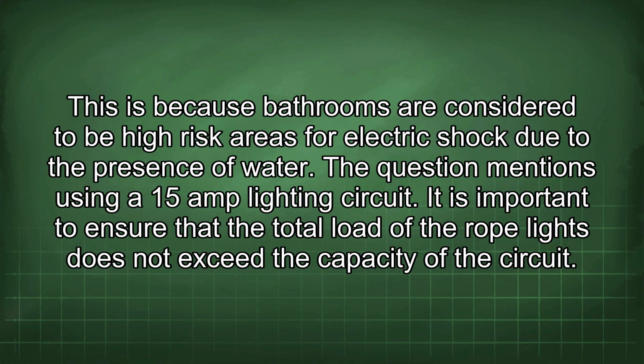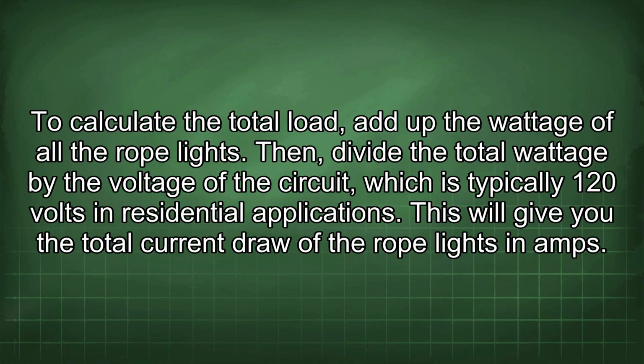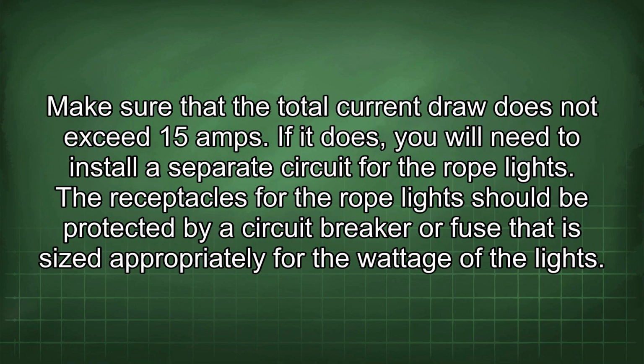The question mentions using a 15-amp lighting circuit. It is important to ensure that the total load of the rope lights does not exceed the capacity of the circuit. To calculate the total load, add up the wattage of all the rope lights. Then divide the total wattage by the voltage of the circuit, which is typically 120 volts in residential applications. This will give you the total current draw of the rope lights in amps. Make sure that the total current draw does not exceed 15 amps. If it does, you will need to install a separate circuit for the rope lights.